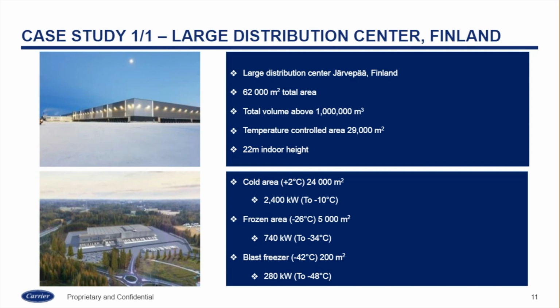Next I'm going to go through the case studies. We have 4 cases to demonstrate the CO2 transcritical product application. The first one is the large distribution center in Finland. This is a country-sized logistics center. The total refrigerated area is about 30,000 square meters, and the total height is 22. It is very big, and it covers the cold area, the frozen area and the blast freezing area within 2 racks of around 3,000 kilowatts of cooling capacity.